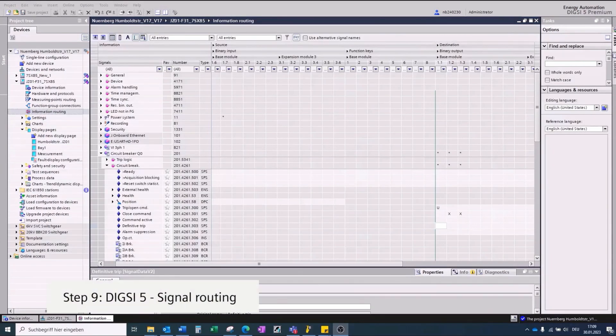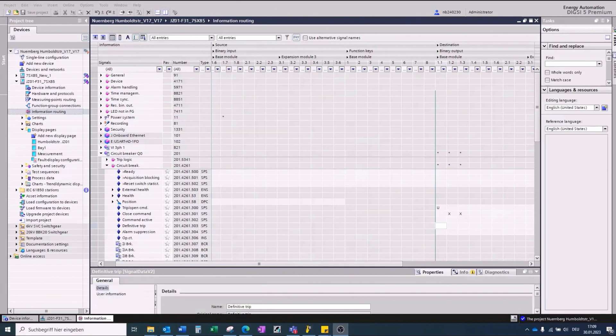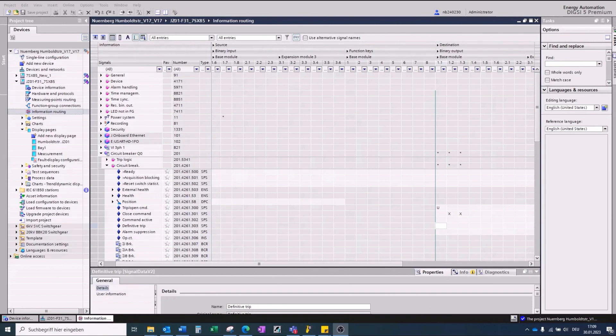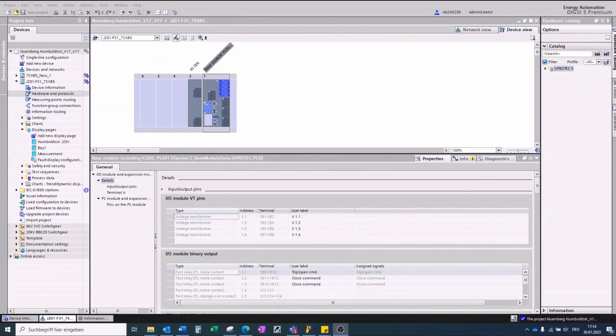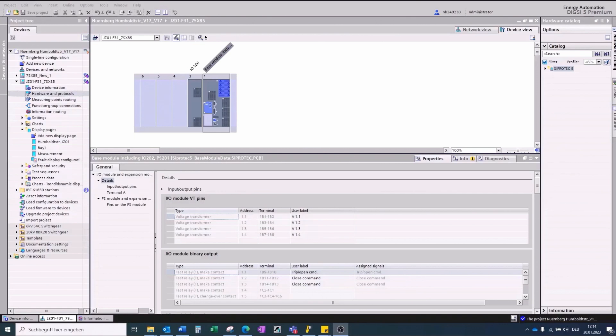Migration Step 9, signal routing. Finalize the signal routing of binary inputs, binary outputs, and LEDs with the information routing editor. We recommend connecting the TRIP command to a fast relay. The information of the binary outputs, contacts, fast or standard, you can get via selecting hardware and protocols.